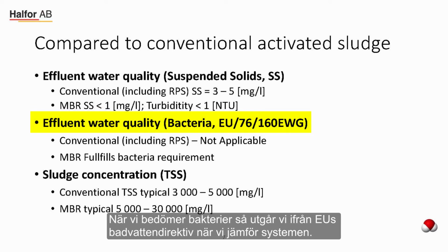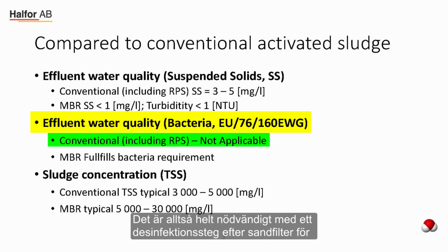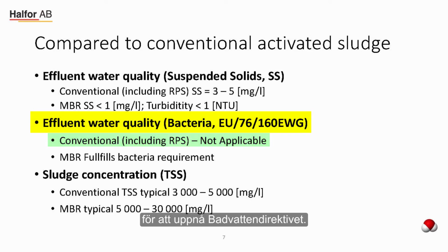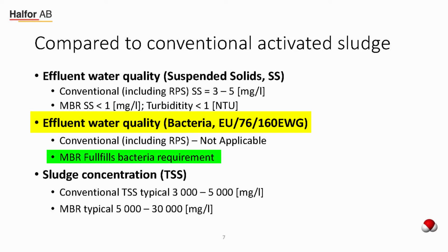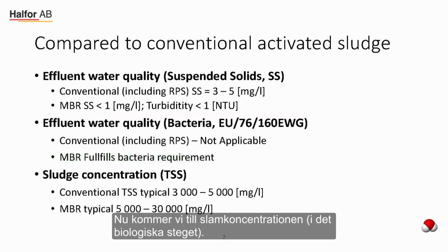Then we will have a short look at bacteria, or more correctly the EU directive, which I've noted down here, in regard to the conventional and the MBR system. With a conventional system, including the rapid sand filter, the bacteria criteria is not applicable. You need the disinfection step after a conventional activated sludge plant. So rapid sand filter will not do the job for the conventional system. With the MBR, as I said before, all-inclusive, will fulfill the bacteria requirement as in regard to the bathing water directive.